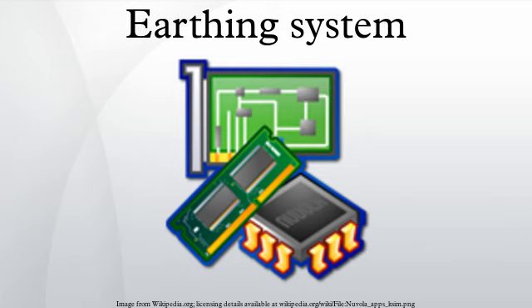In the UK, this system is also known as protective multiple earthing, because of the practice of connecting the combined neutral and earth conductor to real earth at many locations, to reduce the risk of electric shock in the event of a broken PEN conductor, with a similar system in Australia and New Zealand being designated as multiple earth neutral. It is possible to have both TN-S and TN-C-S supplies taken from the same transformer. For example, the sheaths on some underground cables corrode and stop providing good earth connections, and so homes where bad earths are found may be converted to TN-C-S.